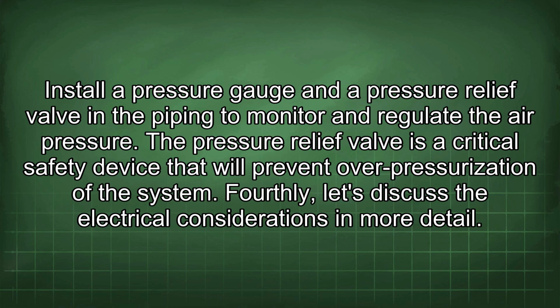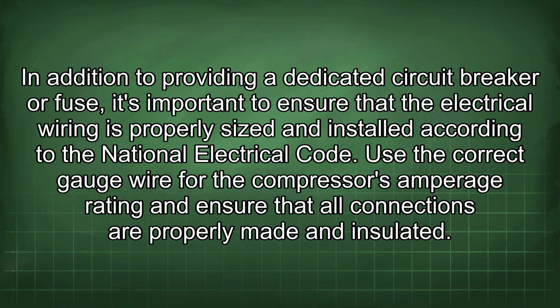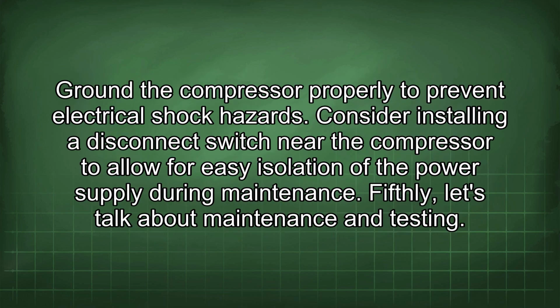Fourthly, let's discuss the electrical considerations in more detail. In addition to providing a dedicated circuit breaker or fuse, it's important to ensure that the electrical wiring is properly sized and installed according to the National Electrical Code. Use the correct gauge wire for the compressor's amperage rating and ensure that all connections are properly made and insulated. Ground the compressor properly to prevent electrical shock hazards. Consider installing a disconnect switch near the compressor to allow for easy isolation of the power supply during maintenance.